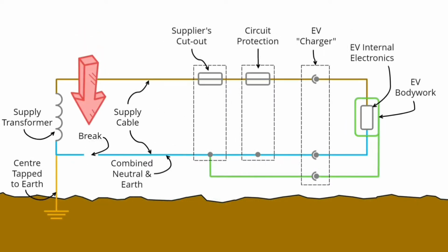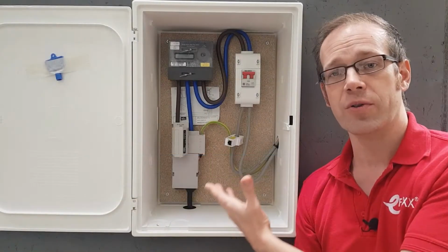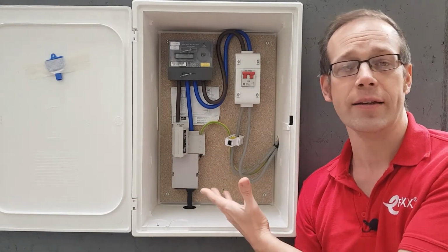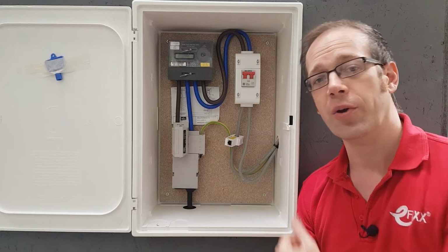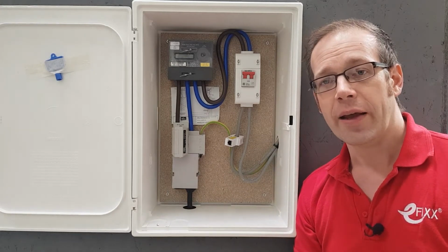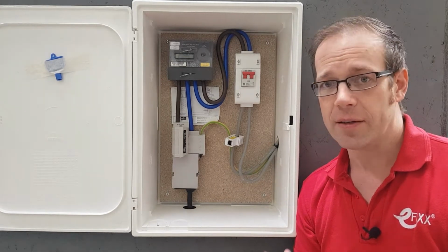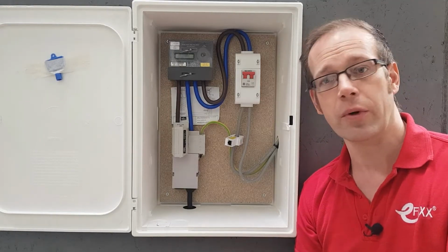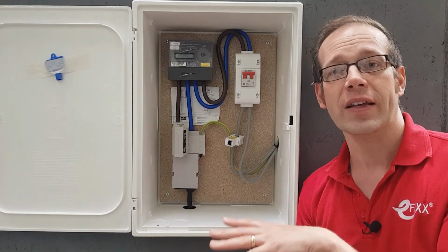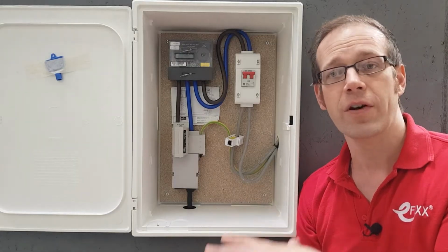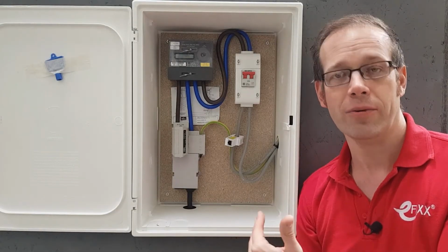Now, if we lose that combined neutral and earth connection in the supply cable, then a big problem occurs. Basically, because the current no longer has a return path, the voltage on the neutral rises to 230 volts, and because the neutral and earth are connected at the origin, all the exposed conductive parts that are connected to the main earthing terminal in the property will rise to 230 volts as well. Now, if someone touches an exposed conductive part and makes a connection to the literal earth that we walk around on, then this could well be enough to give them a lethal shock as the current finds its way back to the transformer down the road.